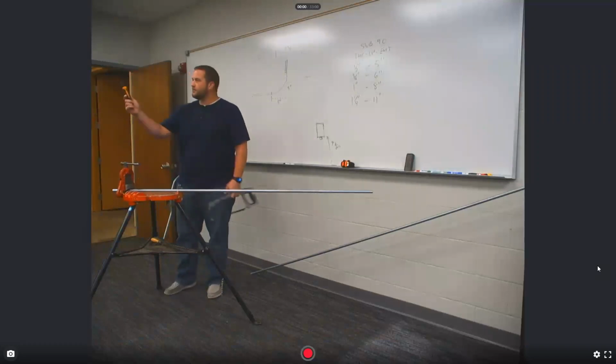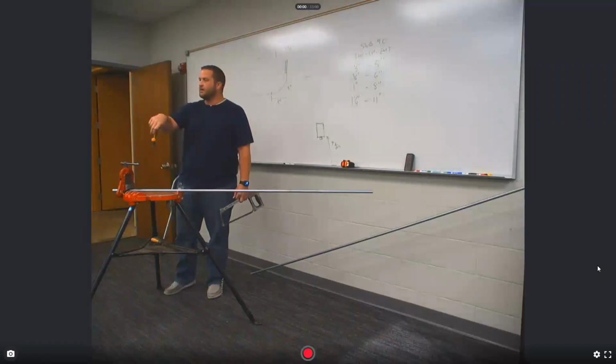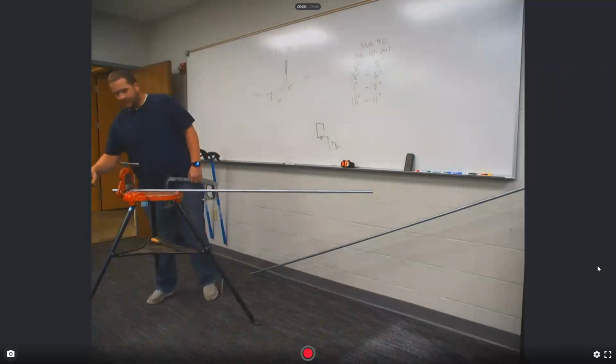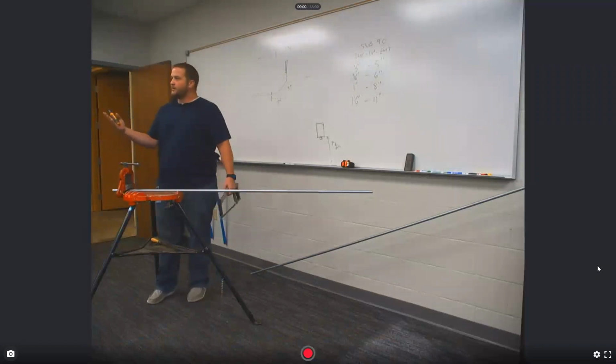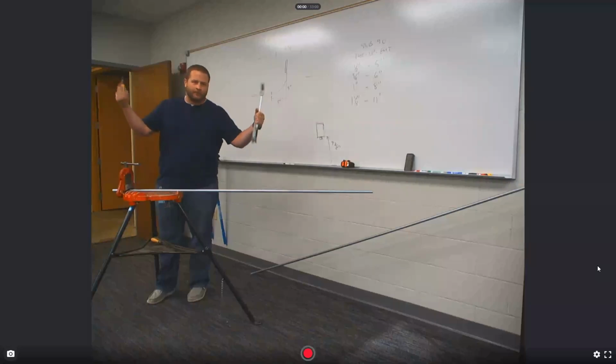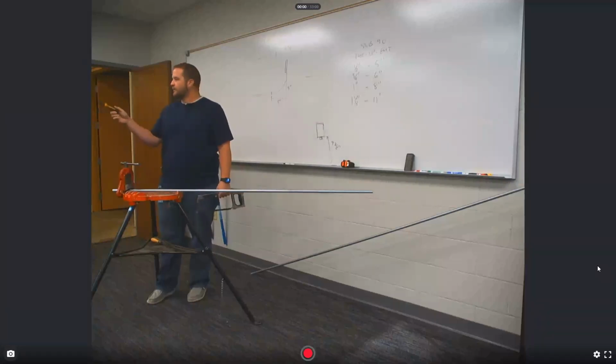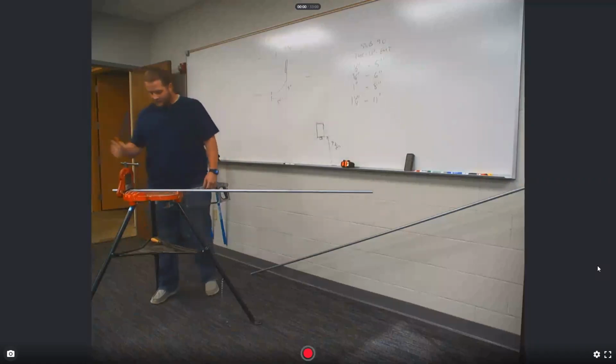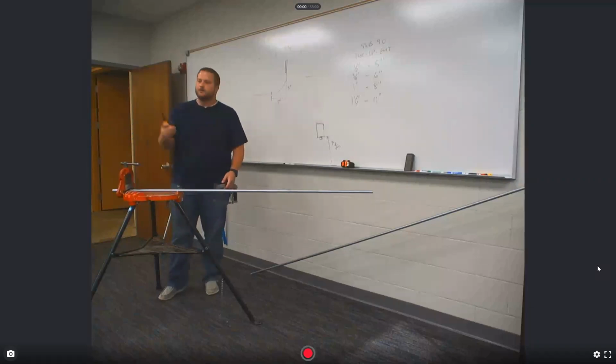I was always taught, file it until you can't. And you guys probably don't have these, a hand reamer. I'm going to leave this back there and hope that it doesn't disappear. You're welcome to use this, but please, when you do your lab, bring it to me and show me, hey, this is my 8-inch 90. And when I look at it, I'm going to check to see if it's reamed. This is called a reamer. You need to ream those burrs out. You can use this. You can use a file. This one is a little bit too big for a 1/2-inch EMT.